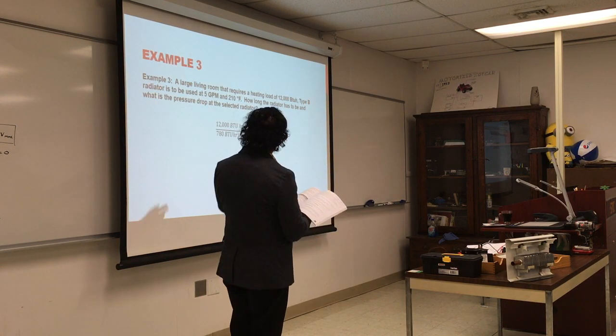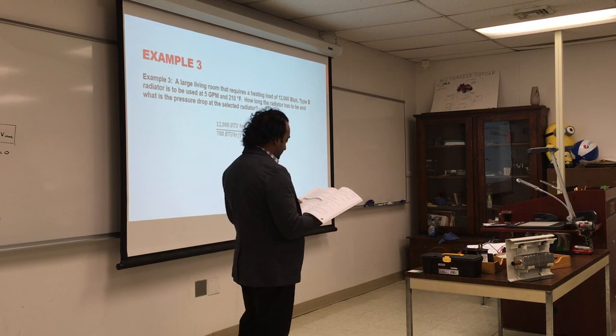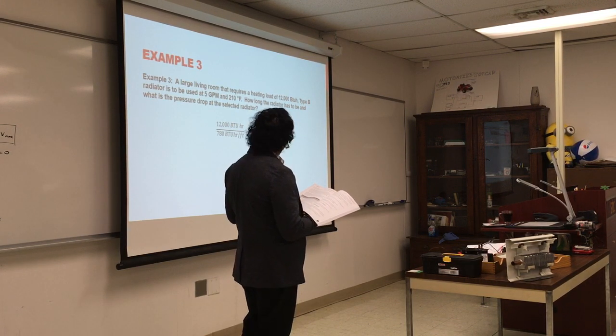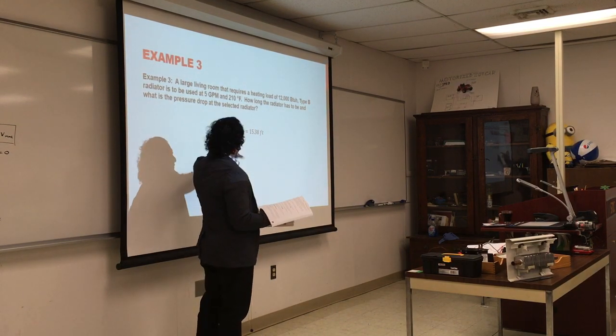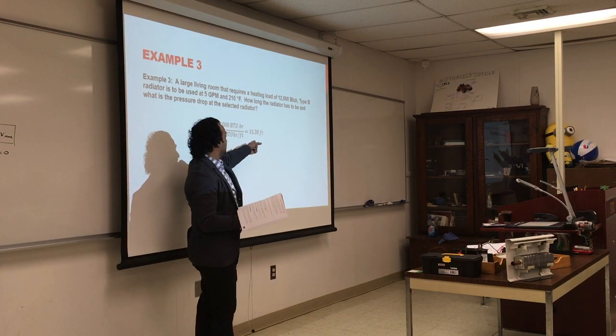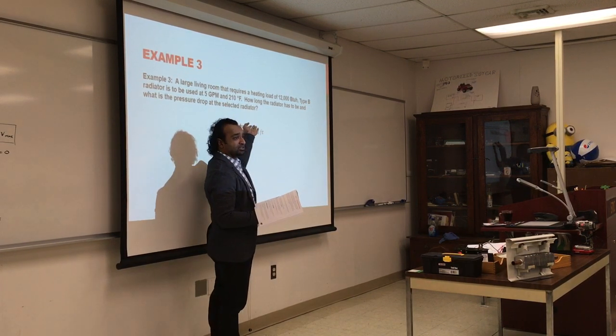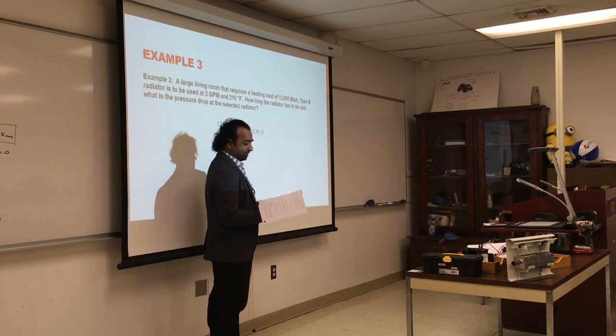Also height is going to be another pump head, we'll talk about that, and also the type of pipe makes a difference. So here, if you look at type B, 4 is closest to 5, and I'm going with 210. So 780 is what you find in your book. I put that in here and got 15.348. I'm going to go up to the next half a foot, so 15.5.